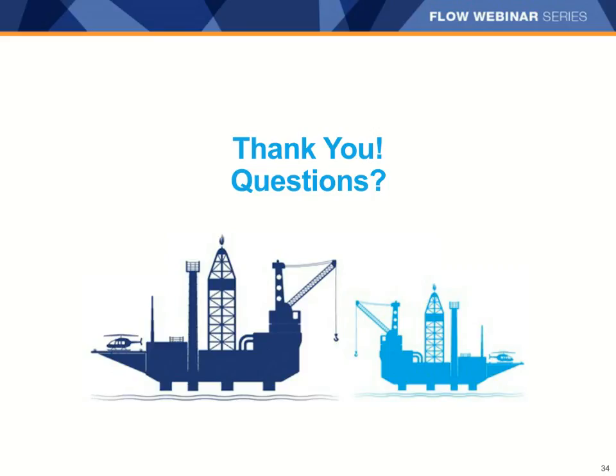We've had questions about pump pulsation quite a bit, and whether a dampener is required and how it's going to impact the flow measurement. I'd state that your primary reason for putting in a dampener wouldn't necessarily be for the flow measurement itself. Dampeners are recommended to protect your pump and the life and efficiency of your pump. Dampeners reduce friction losses on your pump suction and make your pumps more efficient, enhancing life of check valves and improving volumetric efficiency. They also cut down on pipe shaking and vibration, increasing the life of the piping and valves.